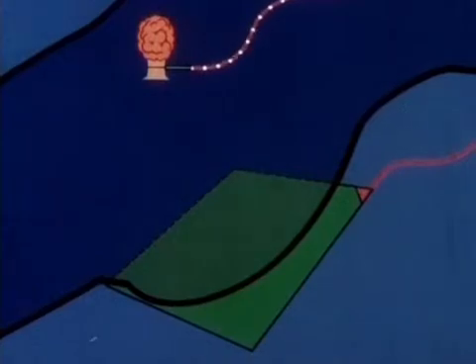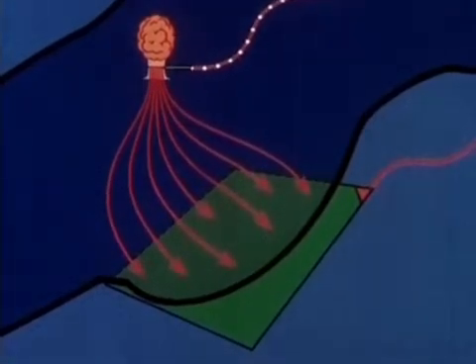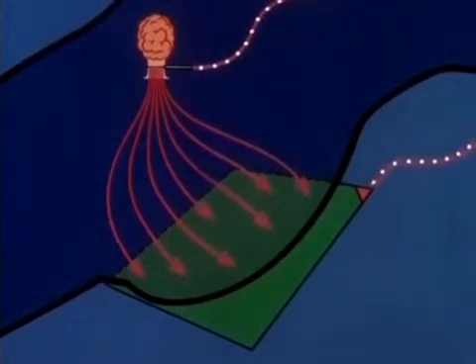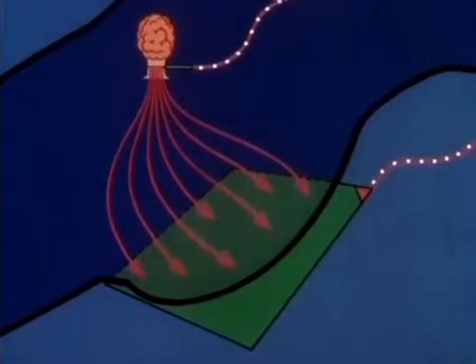To make the circuit there has to be a path back to the electrosurgical unit provided by the patient return plate. When the current is flowing, because the patient plate has a large surface area, the current density at the patient's leg will be very low, so no noticeable heat will be felt there.